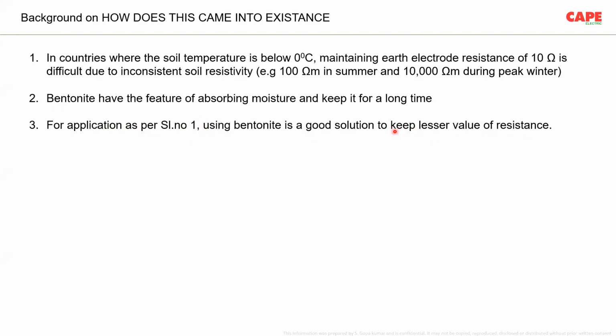So for countries where they have sub-0 degrees, meaning temperature very, very low, in India this is applicable in Kashmir. Wherever the temperature is below zero for a longer time, the moisture content is quite less, and as a result the soil resistivity goes very much up. If you have an earth electrode in soil under that condition for the purpose of lightning current dissipation, and need 10 ohm resistance, then you can use bentonite as an additive material and it really helps.